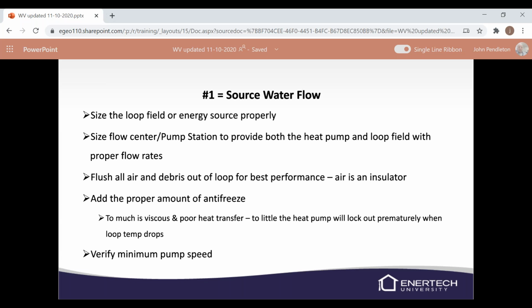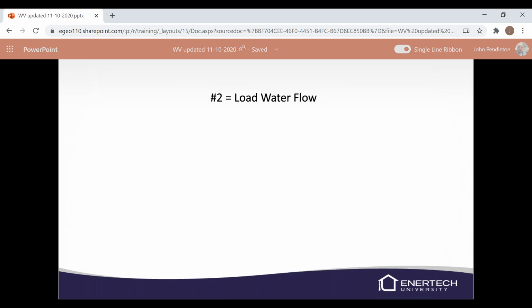We're gonna kind of go through all this pretty quickly. Minimum pump speed is a big deal on source water flow. Again, it's usually up around the 60% mark. So you may want to start up at that point, but just make sure you're sizing pumps properly, loop field, things like that. Load water flow. We've got to have proper water flow. If we're having water flow issues, the unit's going to lock out quite often.